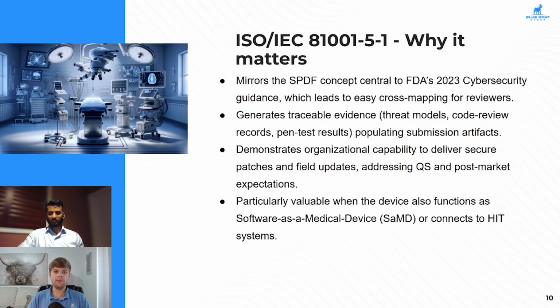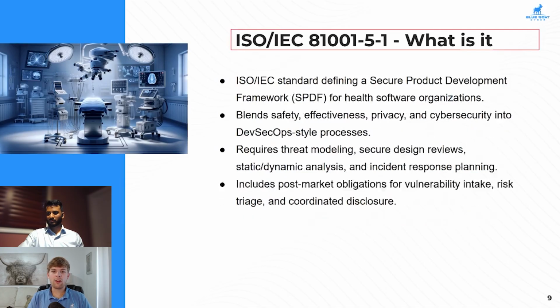Now, why does it matter? This goes right into that secure product development framework that is central to the FDA guidance. This is going to give easy traceability for any FDA reviewers. I'll go back for a second to threat modeling, secure design review, static and dynamic analysis, post-market obligations. All of these are direct obligations when submitting to the FDA under the current guidance. So adhering to IEC 81001-5-1 is often going to build in all of the infrastructure, systems, and processes that you'll need to adhere to FDA compliance when it comes time for submission.